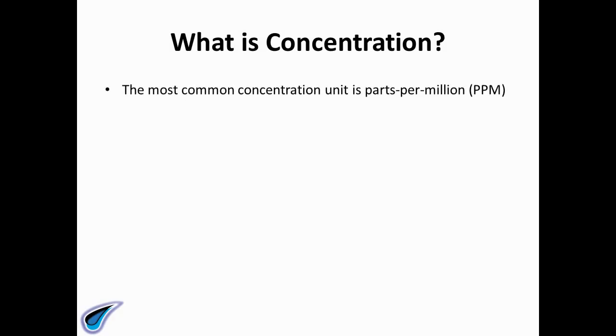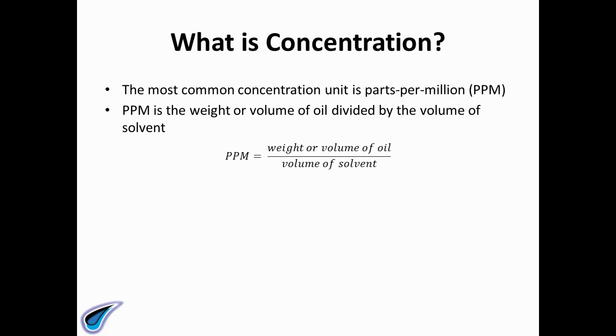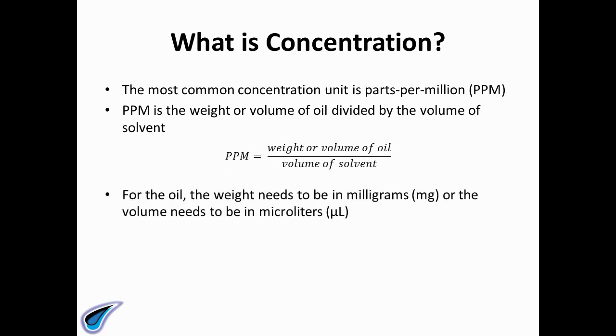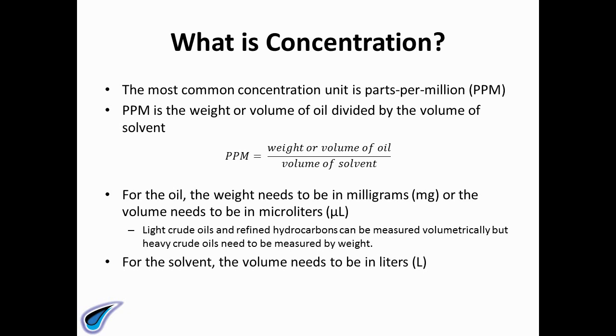The most common concentration unit is parts per million, ppm. Ppm is the weight or volume of oil divided by the volume of solvent. For the oil, the weight needs to be in milligrams or the volume needs to be in microliters. Light crude oils and refined hydrocarbons can be measured volumetrically, but heavy crude oils need to be measured by weight. For the solvent, the volume needs to be in liters.